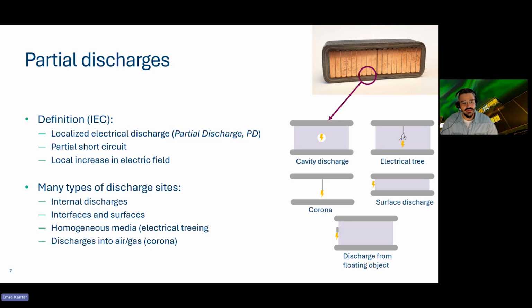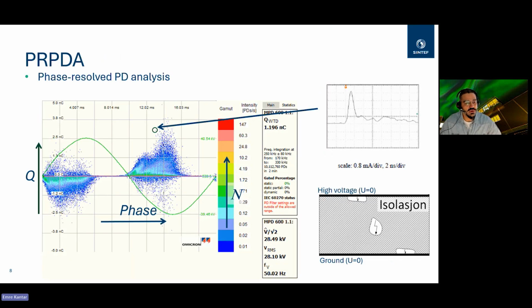There are different types of degradation mechanisms, but for us the most relevant one is the cavity or delamination discharge. I'm just speeding up a bit. These cavities form between the insulation material and the copper, as I also showed in the previous slide. A partial discharge is seen in a phase-resolved plot like this. Every single dot in this image refers to a single discharge event. As you see, there are millions of these dots, meaning millions of partial discharges happening on these voids and delaminations. Over time, if they are exposed for a long time, they can grow and lead to complete failure.